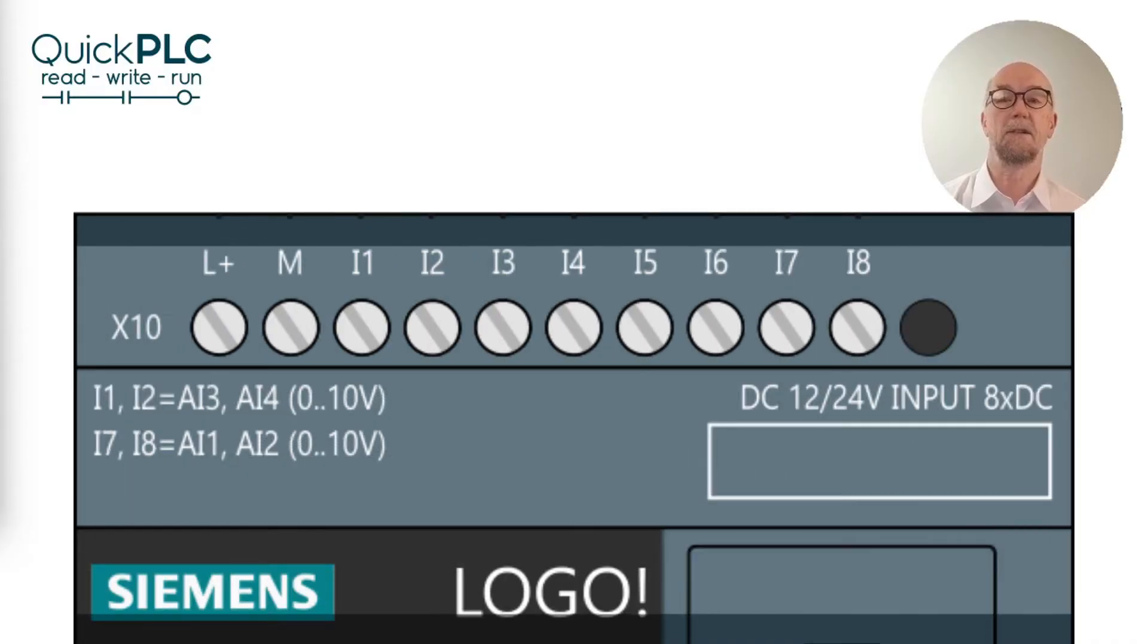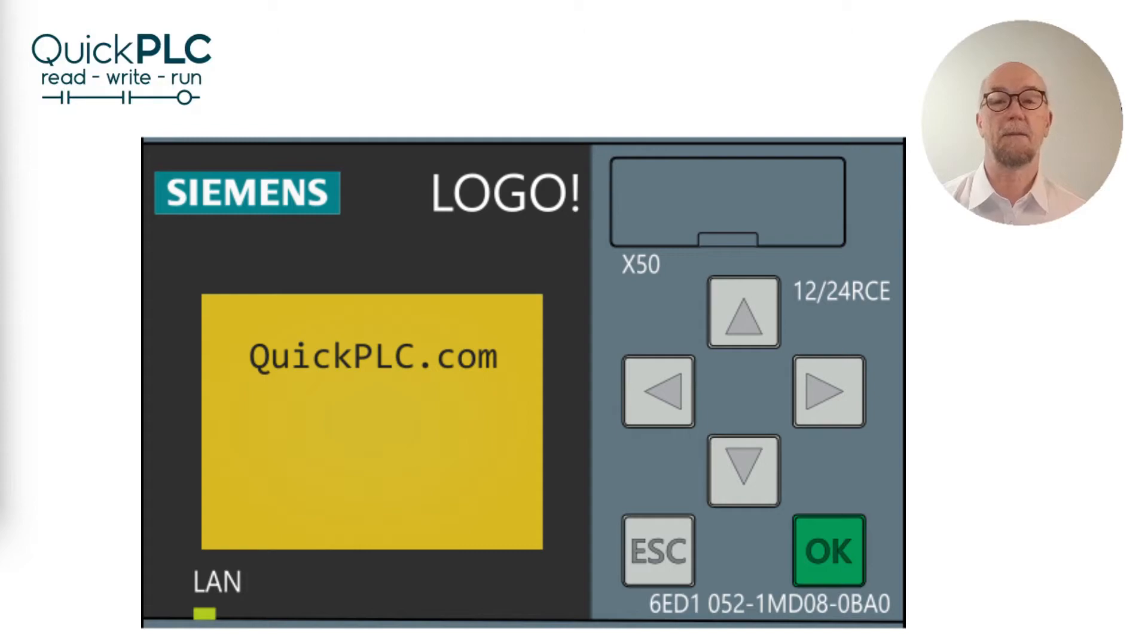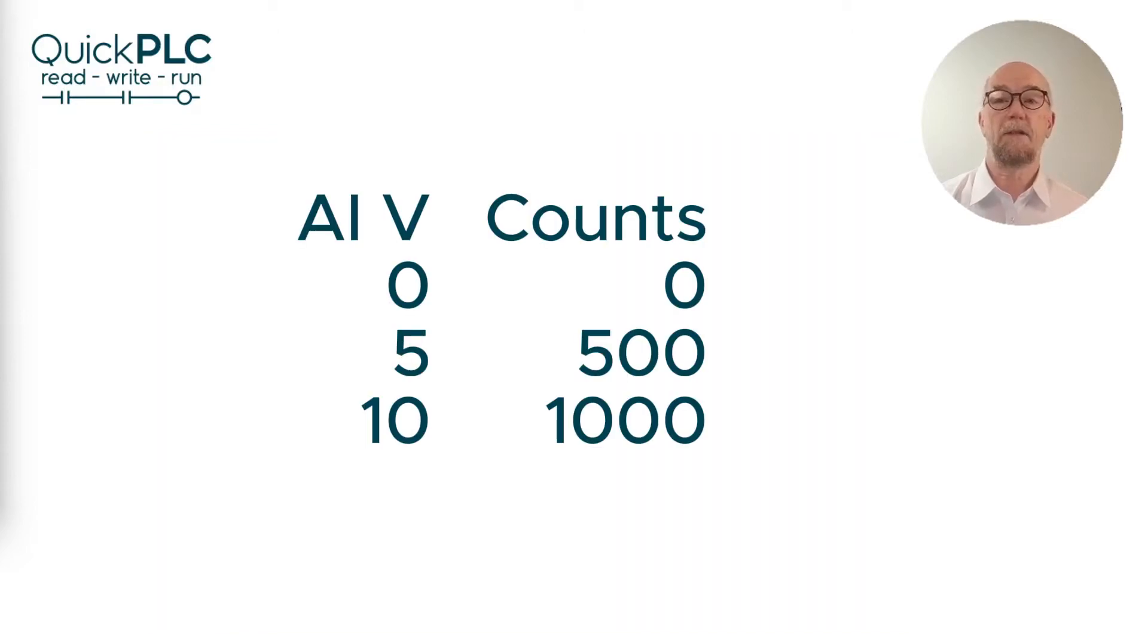Configuration is done through the Logo interface or through LogoSoft. A zero to ten volt input will result in an internal count of 1000. A zero to five volt signal can be used, but this will result in loss of half the resolution and the maximum reading will be 500.